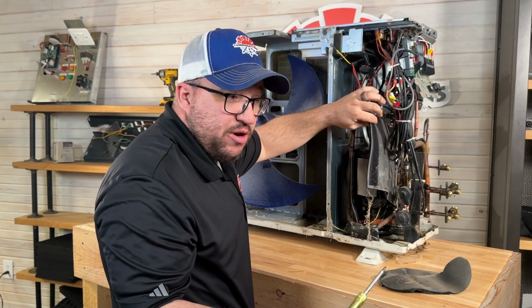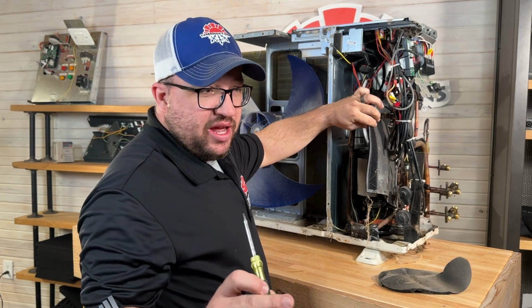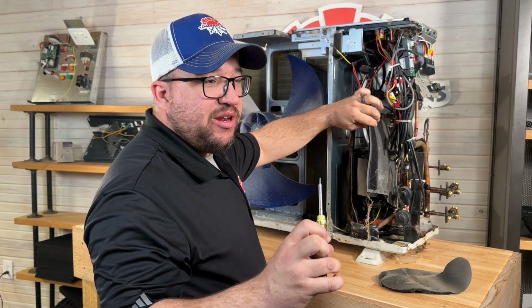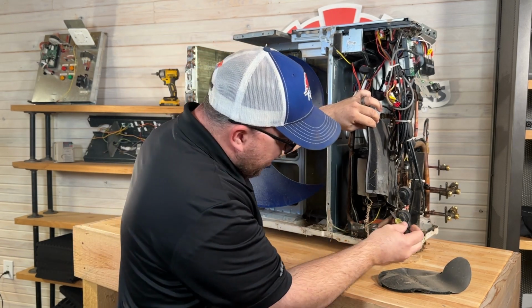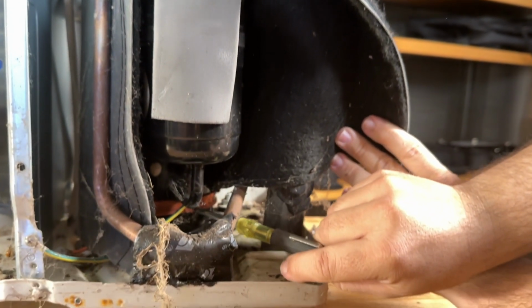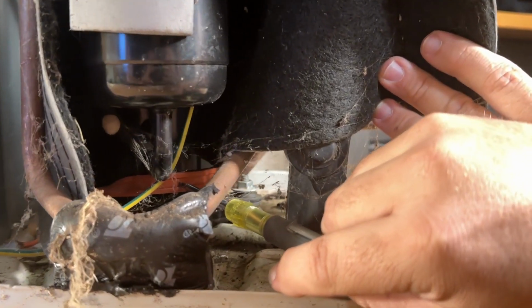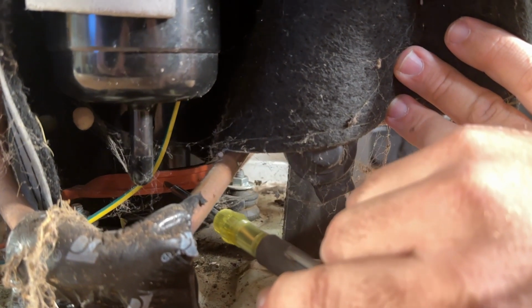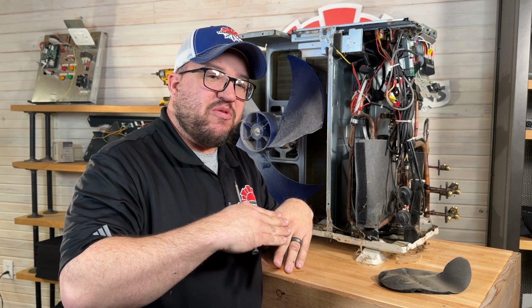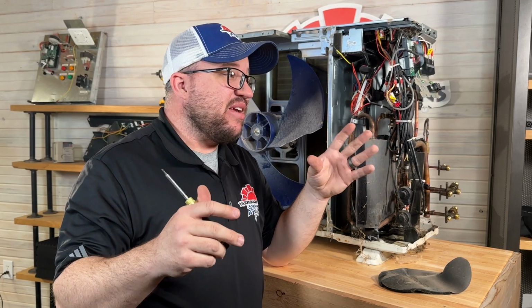One thing you'll see on this compressor, and this should be on every unit, I don't know why they don't make this standard, but a lot of standard units will not have this, is a crankcase heater. And that crankcase heater is going to be great because refrigerant likes to migrate below the oil level. And when it does that, it can actually push the oil out of the compressor. That is a big problem.